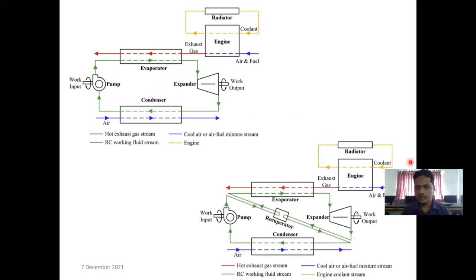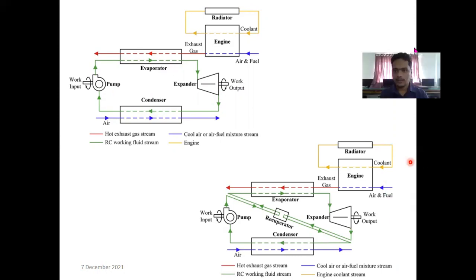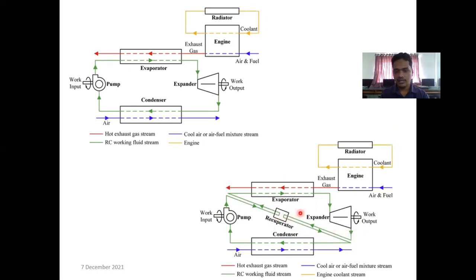Another kind of arrangement: we supply air and fuel as input to the engine; the engine develops some work and emits exhaust gases containing a large amount of heat. That heat is used as the input source to the evaporator. The pump pumps water, which is converted into steam, and the steam expands for power output. Here we also place a recuperator — a device that captures waste heat from the exiting steam and gives it back to the evaporator. This is one kind of arrangement.